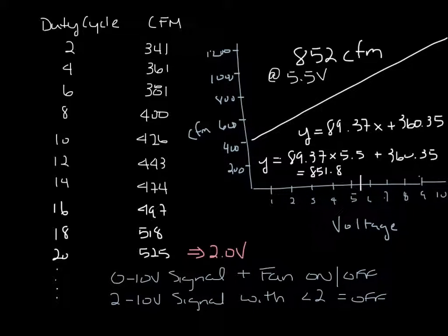Now this opens you up to all sorts of control options. For instance, you can change the zone CFM based on different seasons or for night setback. So that's how you can control your CFM on a fan box with an ECM motor.